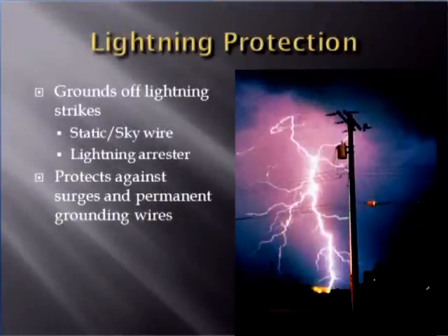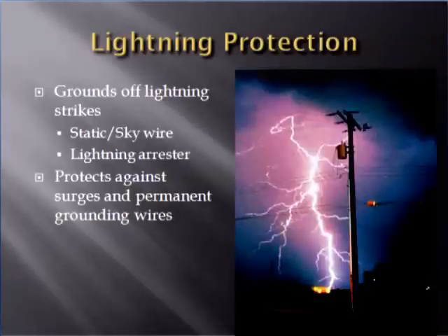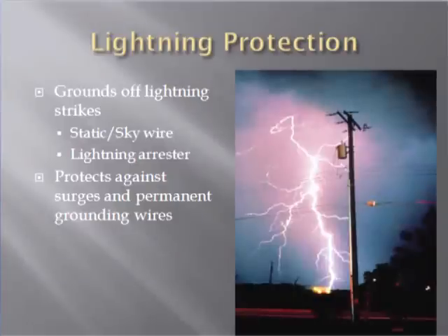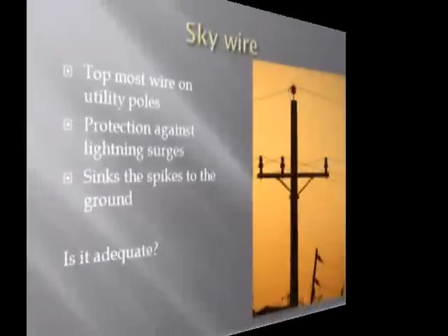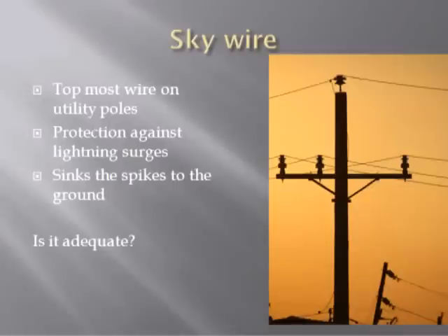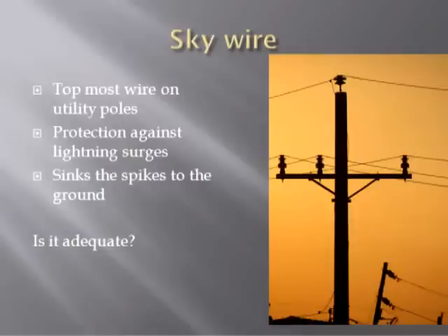The most basic part of line protection is lightning protection. Poles are high in the air and are prone to lightning strikes. A flashover damages insulation and causes a permanent ground fault. Two methods are used to avoid this: a sky wire and a lightning arrester. The sky wire, or static wire, is the utmost top line of the utility pole. This wire bleeds off lightning surges from power lines when lightning strikes during a thunderstorm. The static wire is connected to the grounding conductor.